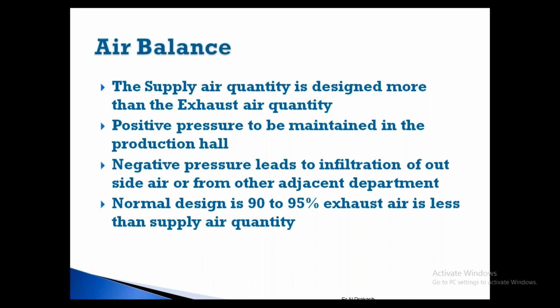That is, supply air should be slightly more than the return air. Return air should be less, only 95% of the supply air. Why? The reason is that it will create a positive pressure inside your department, so that outside infiltration air doesn't come inside your conditioned space. So more positive air is there.